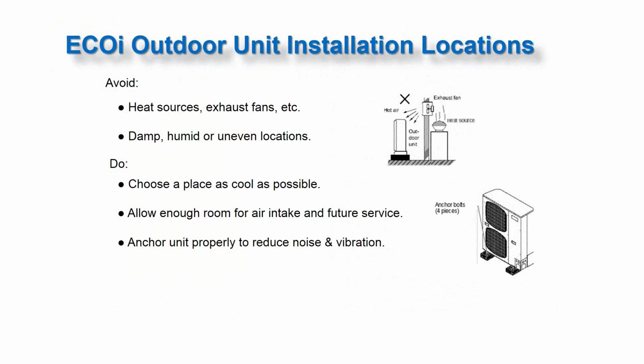Okay, this slide here is our ECOi outdoor unit installation location. So we want to be very careful where we install our condensing unit, our outdoor unit. We've got to keep an eye out for certain things. So we want to avoid heat sources such as exhaust fans. We want to avoid damp, humid, or uneven locations. What we want to do is choose a place that's as cool as possible. We want to allow enough room for air intake and future service, and we want to make sure that we're able to anchor properly to reduce noise and vibration.